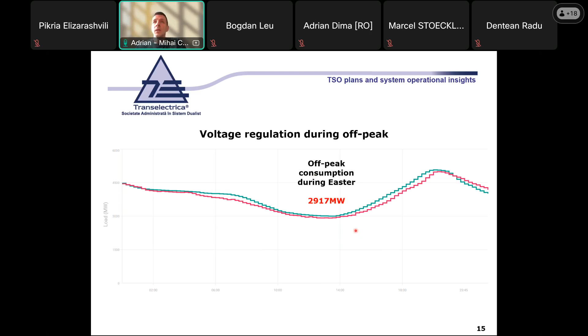From the operational perspective, we are forced to take a lot of measures, and we prepare specific schemes to cope with the high voltages we see during this period of year. I'll present later that we also make some investments to mitigate these issues, but for now it's quite a challenge. Last year during Easter, the off-peak load was almost 3,000 megawatts, considering the average load is 7,500 - so it's even less than half of the average load.